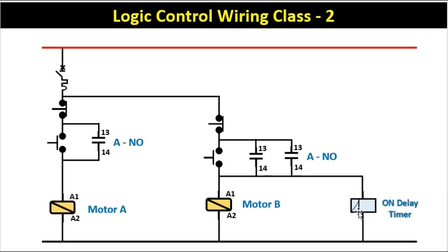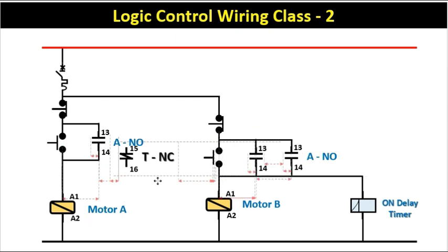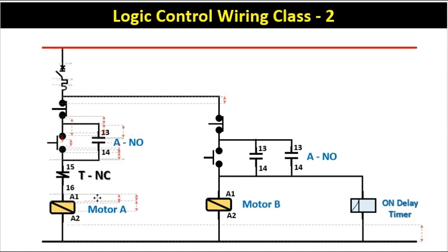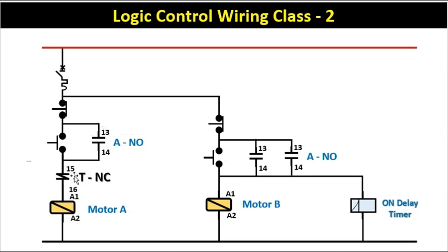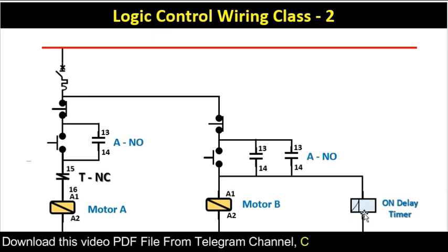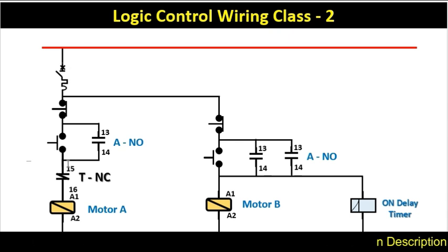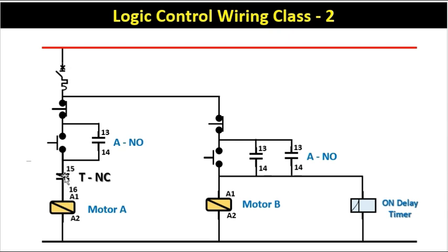In this timer, there is an NC contact. We use this NC contact to turn off motor A — we connect it in series to motor A. The advantage is that when the timer's set time is completed, the contact changes. When the NC contact changes to NO, power supply flowing through motor A's circuit will break, and motor A will turn off automatically.